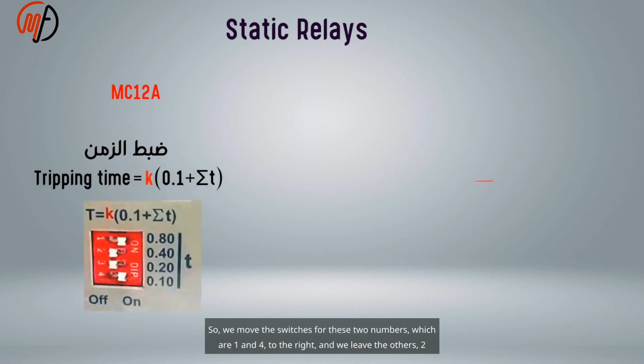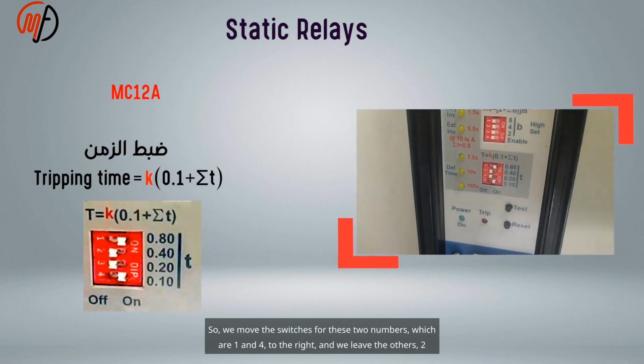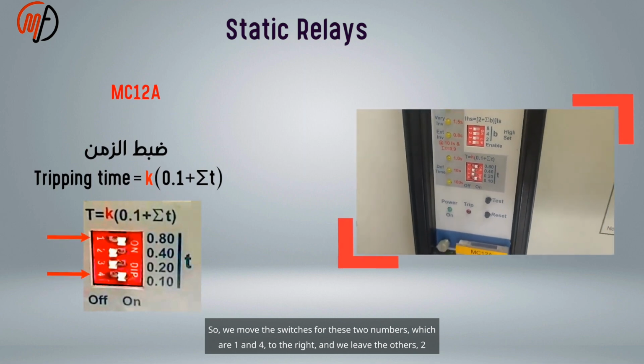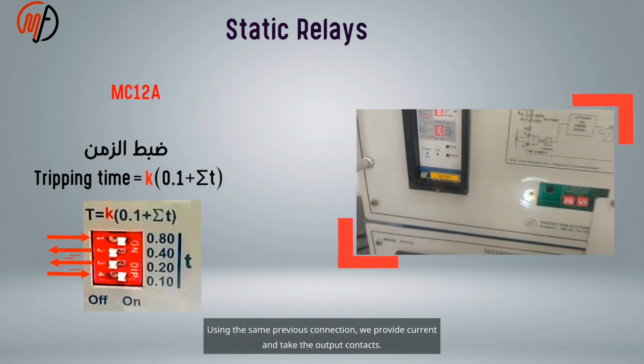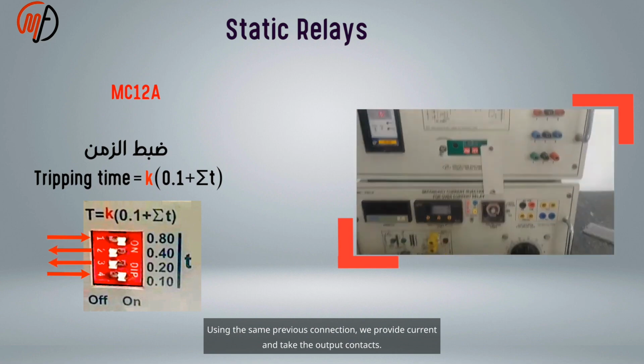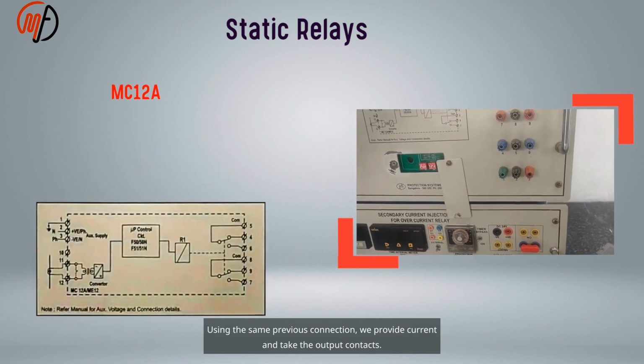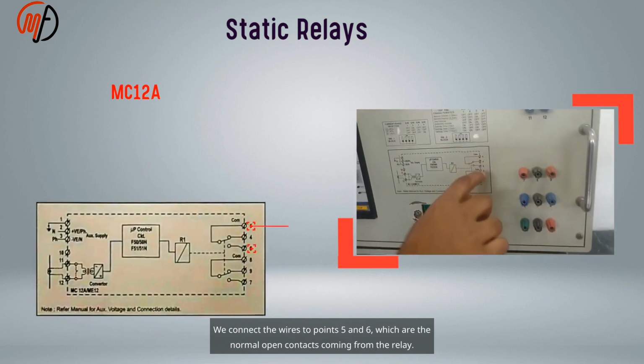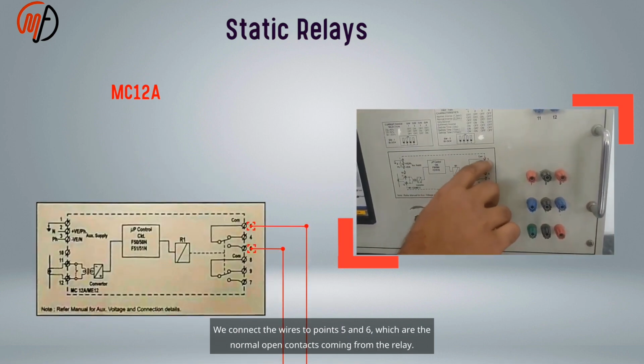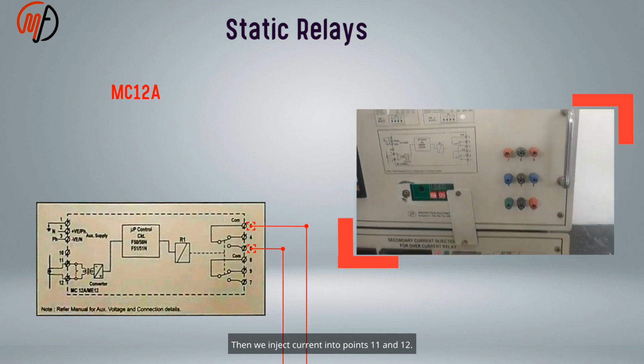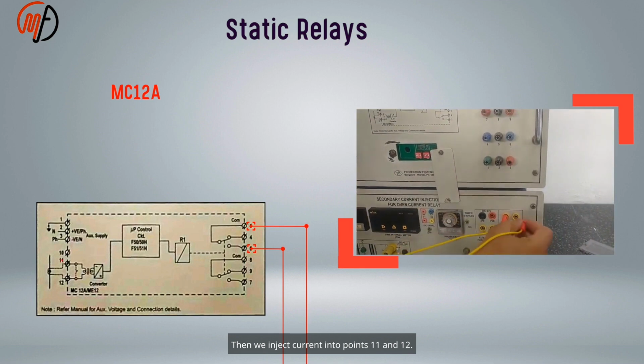So we move the switches for these two numbers, which are 1 and 4, to the right, and we leave the others, 2 and 3, to the left. Using the same previous connection, we provide current and take the output contacts. We connect the wires to points 5 and 6, which are the normal open contacts coming from the relay. Then we inject current into points 11 and 12.